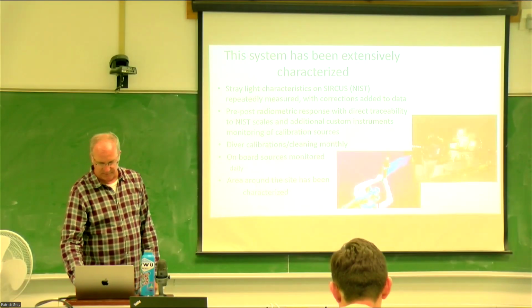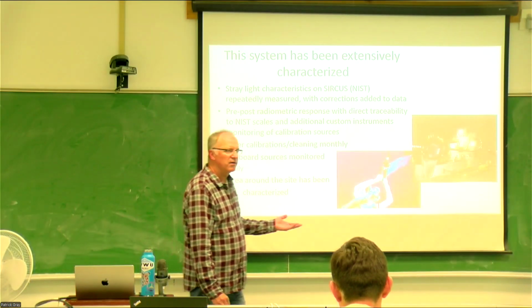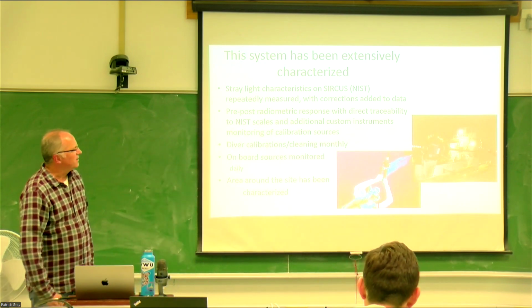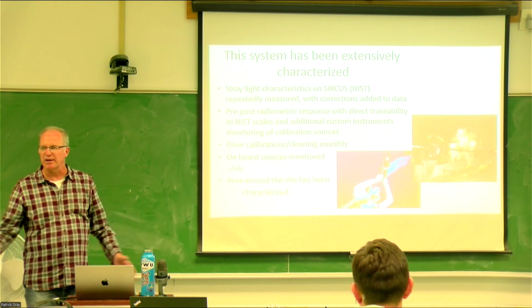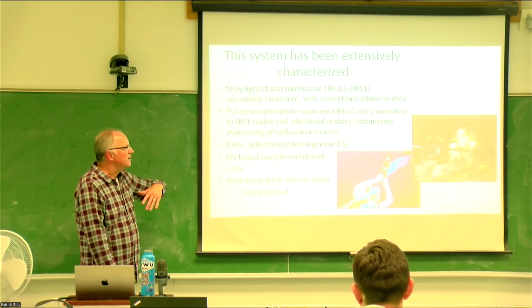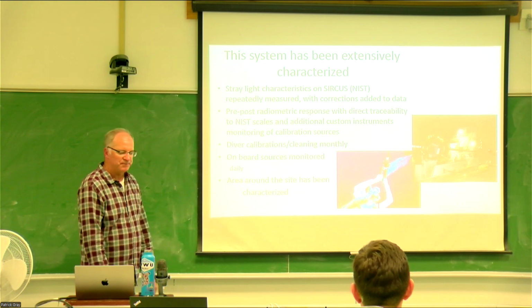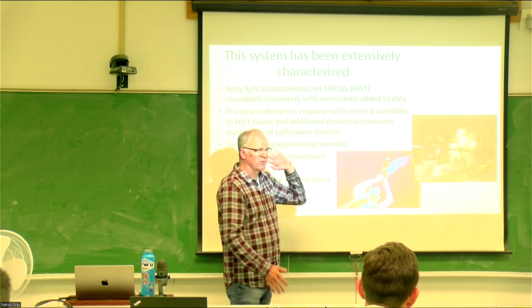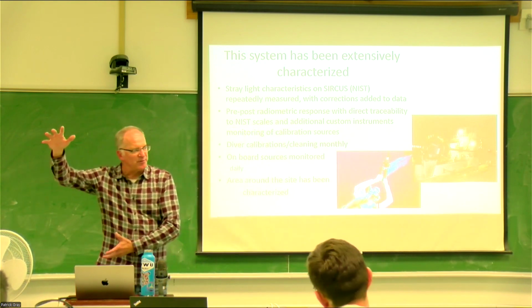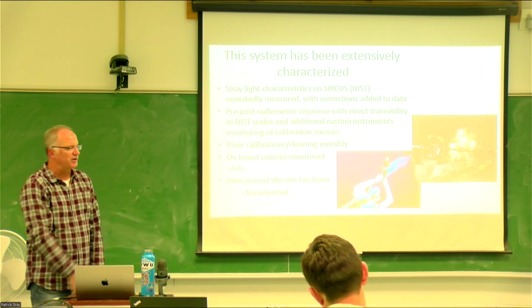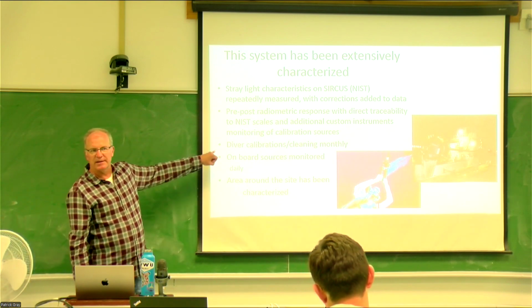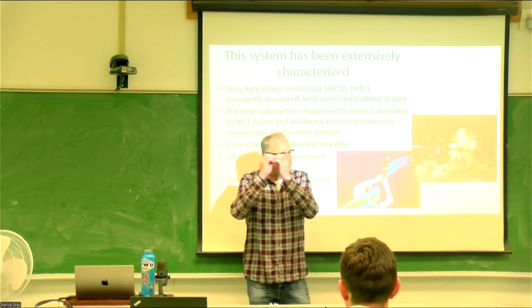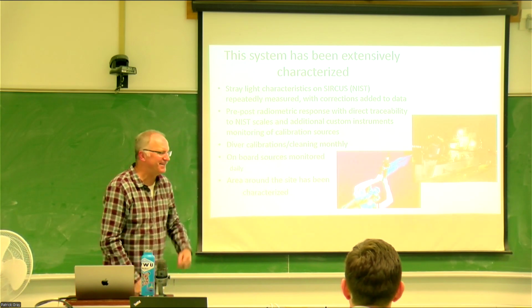All right, the MOBY system, like I said, has been around for a long time now. It has been very extensively characterized. They've studied stray light bouncing around inside the system and done a lot of pre- and post-calibrations. MOBY was on a routine of every 6 months: that whole tethered attachment part would get pulled out and a brand new one put in. But monthly, they would go out, put divers in the water with tiny cleaners, and clean the windows and the faces.